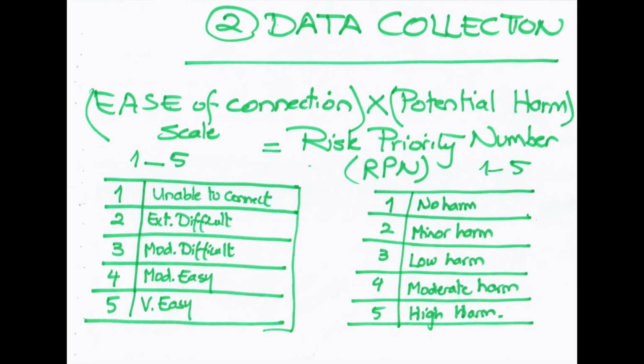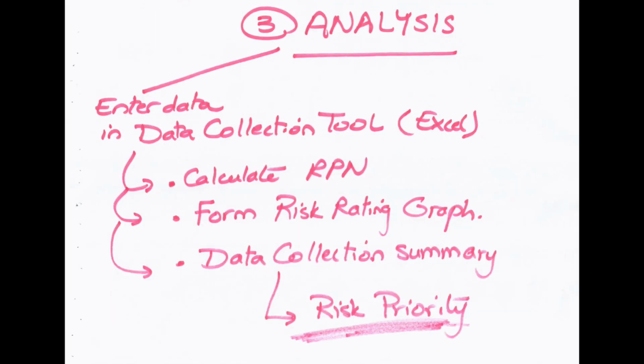For the data collection, we will use what's called the risk priority number. This risk priority number will consist of ease of connection scale times potential harm. Each ease of connection scale from 1 to 5, 1 unable to connect and 5 very easy to connect, times the potential harm, 1 is no harm and 5 is high harm. After data collection, we will enter it in a data collection sheet in the form of an analysis Excel spreadsheet, which will calculate the RPN, form a risk rating graph, and risk priority summary.